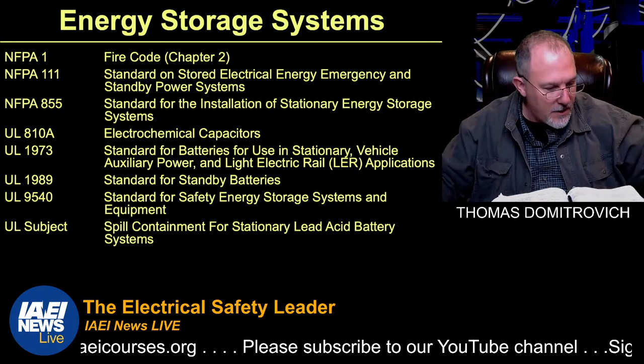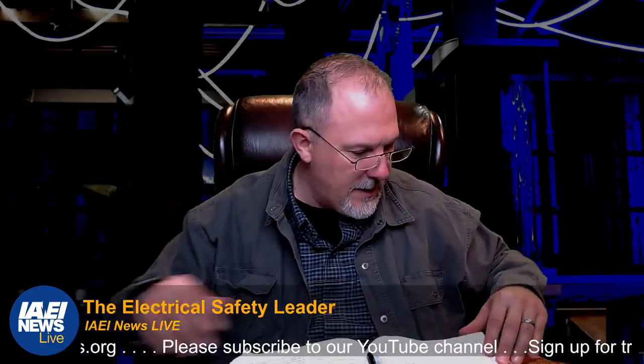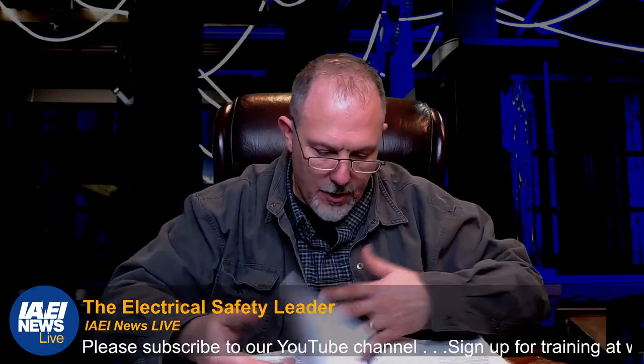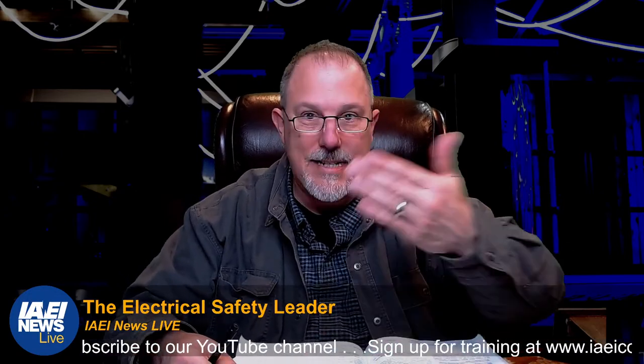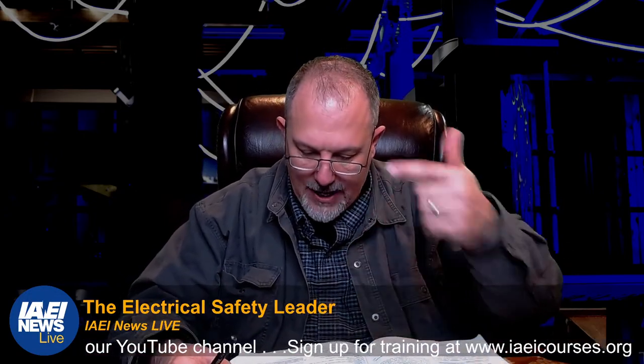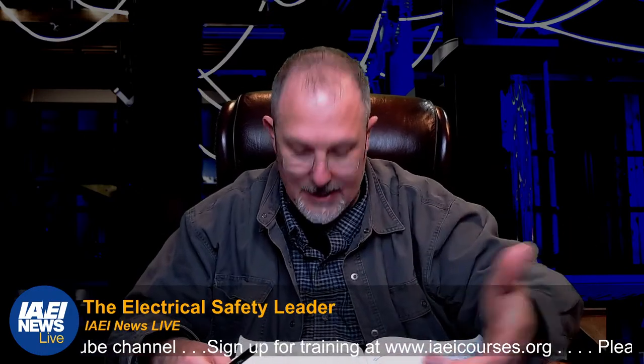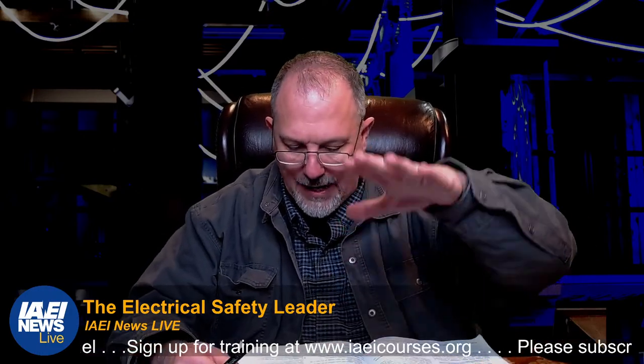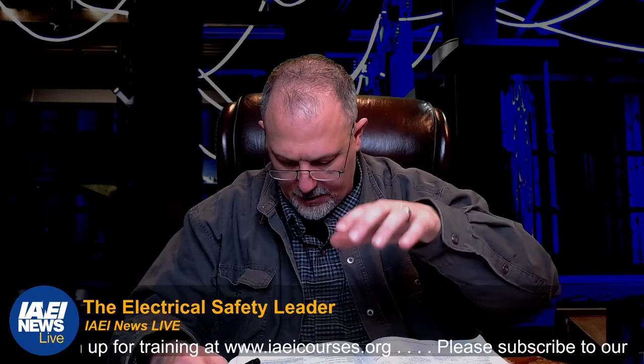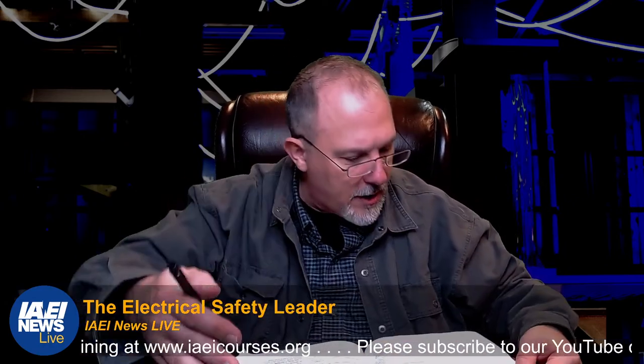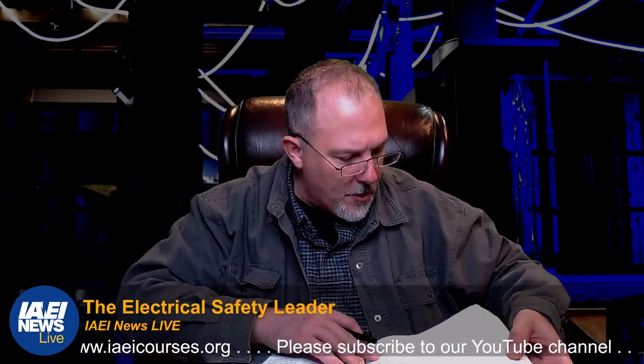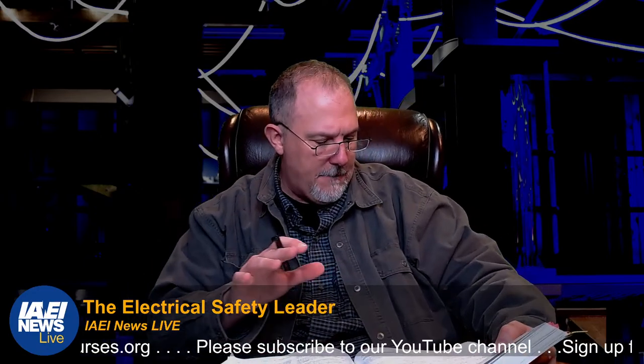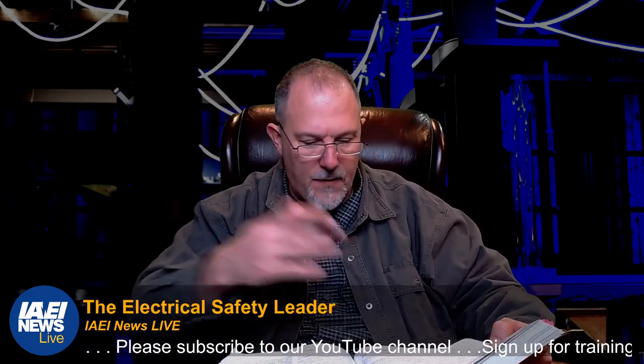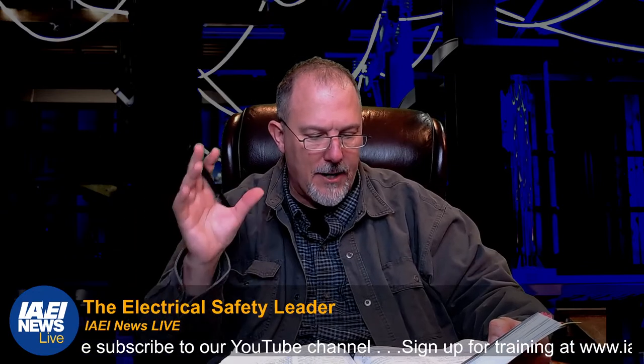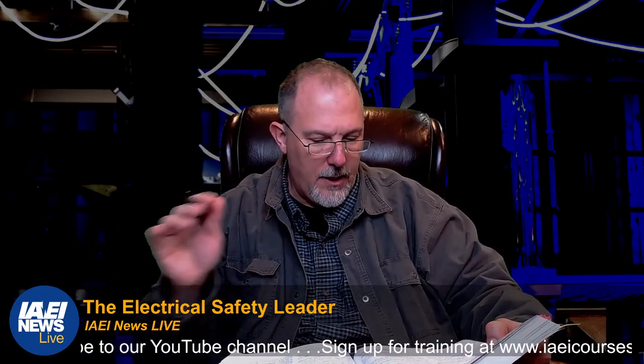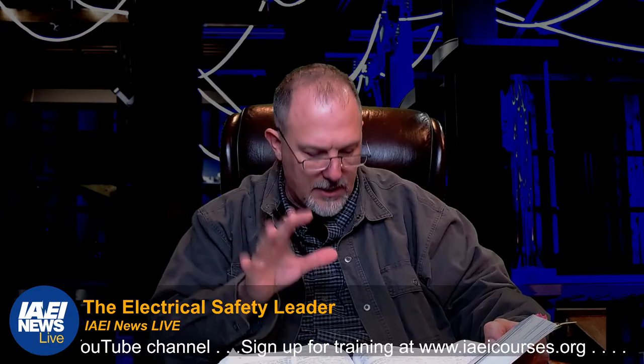So let's take a look. Part one is general, part two is your disconnecting means. You're going to have a means to disconnect the energy storage system, and they give you guidance on the location, the control, the notification and marking requirements, the warning labels, the remote activation, and connection to energy sources.